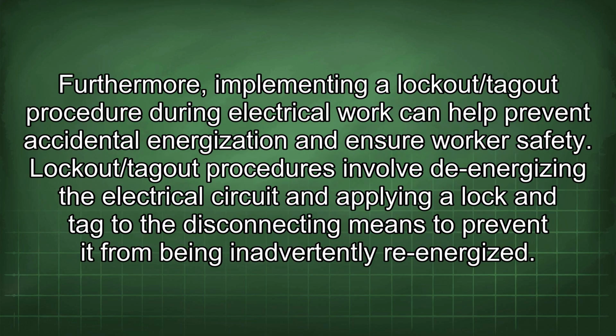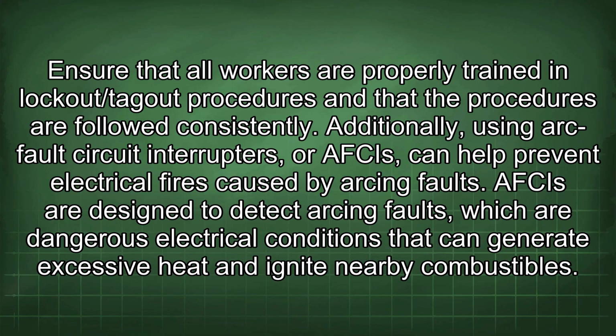Furthermore, implementing a lockout/tagout procedure during electrical work can help prevent accidental energization and ensure worker safety. Lockout/tagout procedures involve de-energizing the electrical circuit and applying a lock and tag to the disconnecting means to prevent it from being inadvertently re-energized.